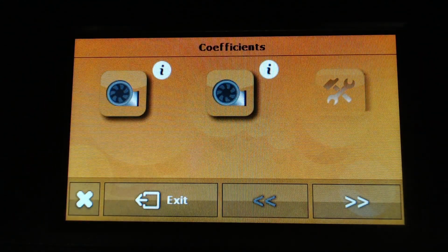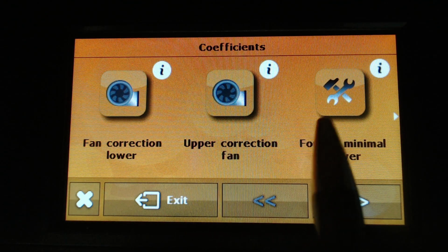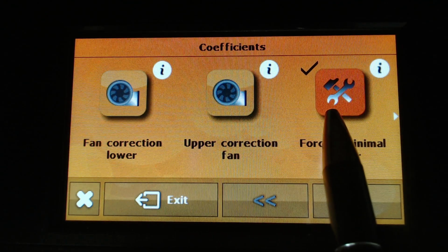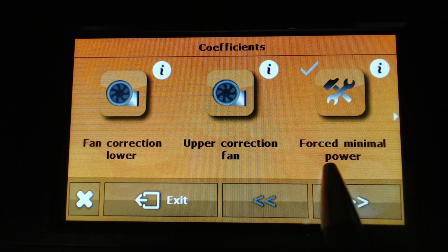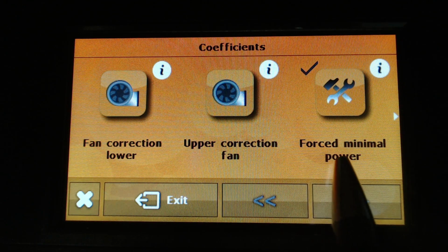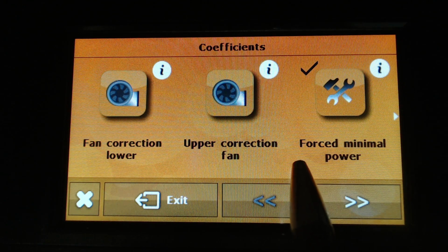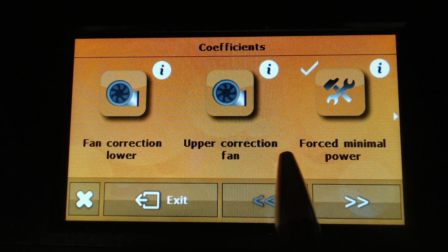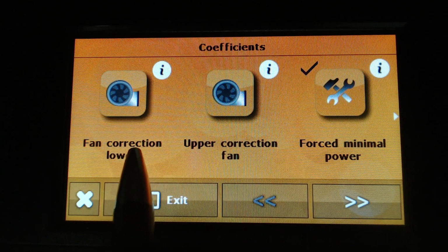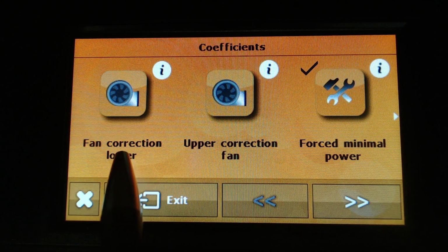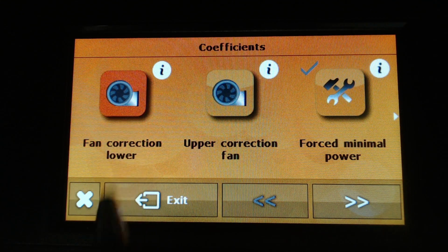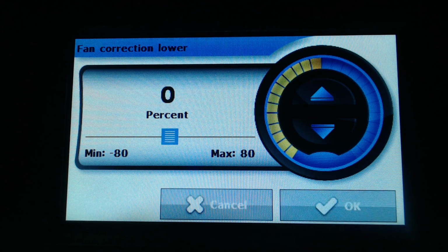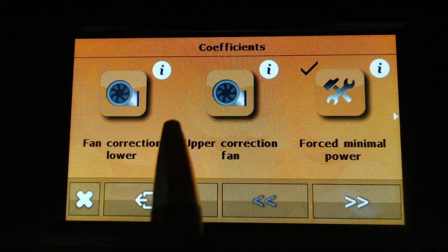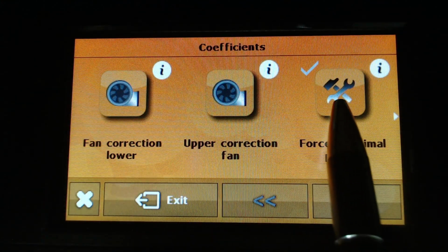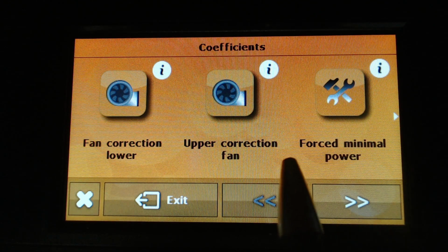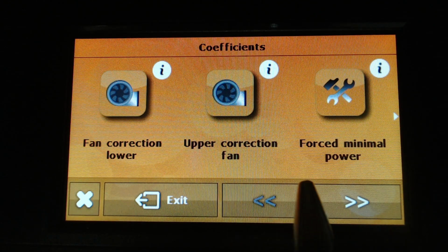speed of the fan. If you want to see the minimal power, you can force the boiler to work only at minimal power. If you push this function, then wait 5 minutes, then you can check the minimal power flame and do the same correction for fan correction lower for min power of the boiler, again in the same way. Then of course after your corrections, don't forget to deactivate this function so the boiler operates again in a normal way.